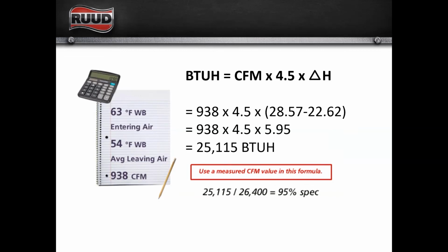So it may be that it's undersized, right? It may be that it's undersized because we've got some insulation issues. We could have an issue where some windows are cracked. I mean, there's a lot of reasons. If we did the calculation and we came back that we were operating at 18,000 BTUs, well, now we got another problem that we need to look at, right? Did we properly measure and calculate, wet bulb to enthalpy? Are we moving the right amount of air? Do we have a charge issue? Do we have something else going on with the system or with the application?